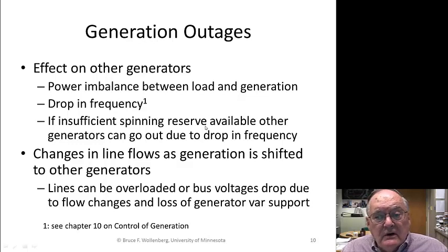What if I lose a large generator? And it's simply a matter of doing an accounting of how much the largest generator that could be lost. Sometimes it's the two largest generators I have to carry in a spinning reserve. Line flows can change as generation is shifted to other generators, so that's another check that you can make as a what-if test.